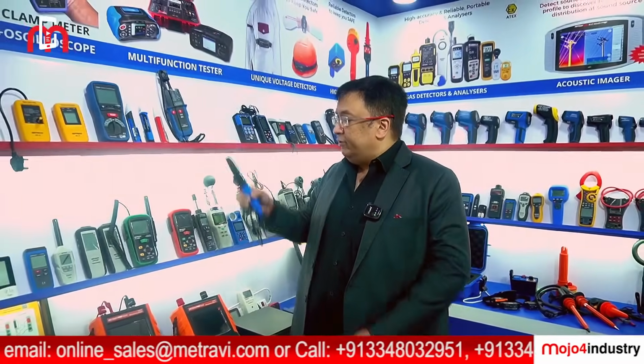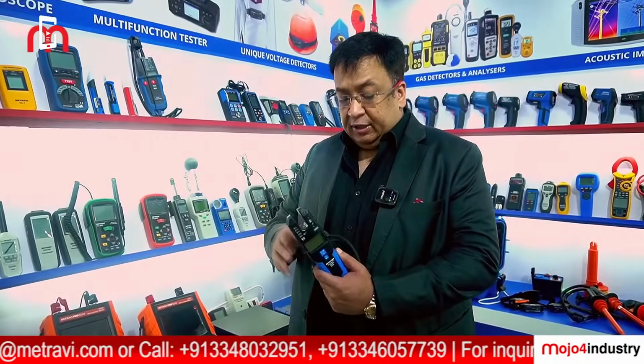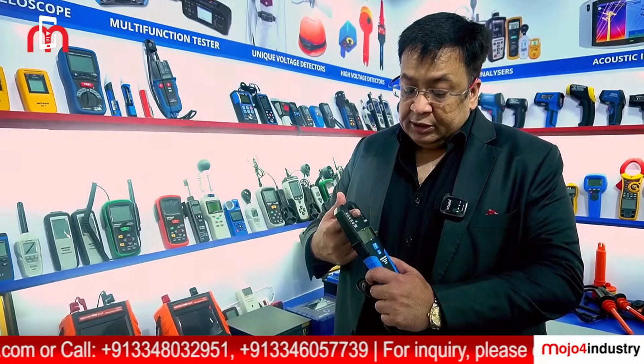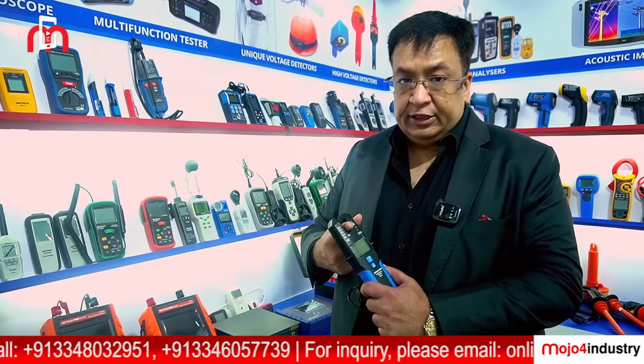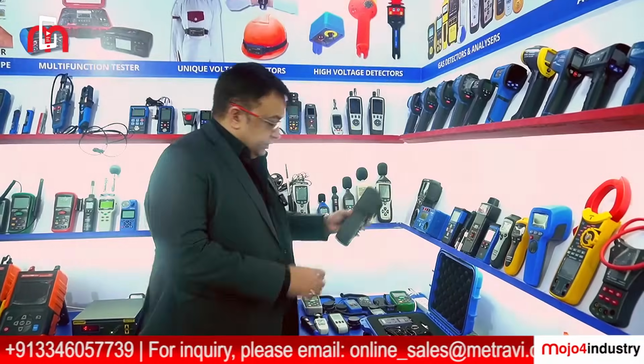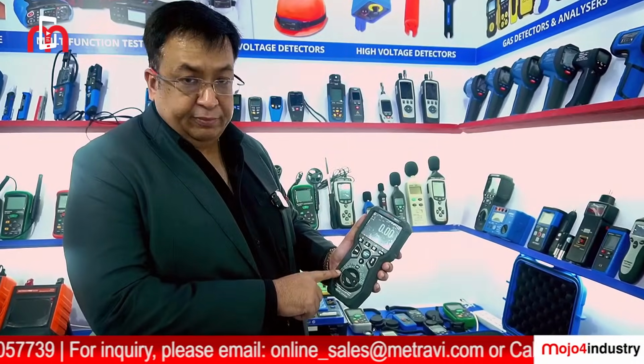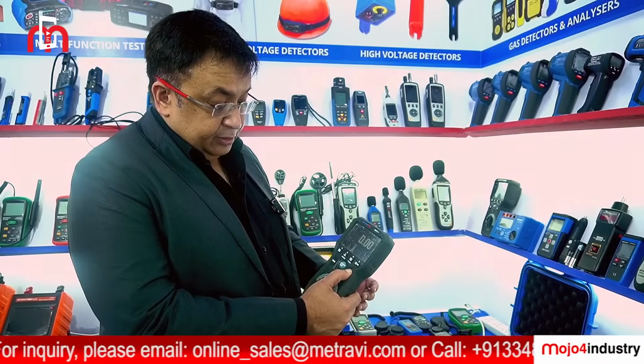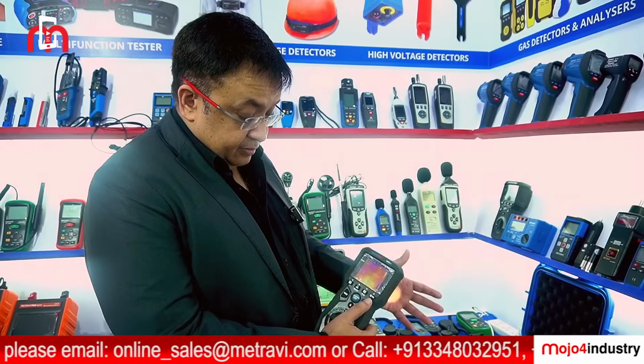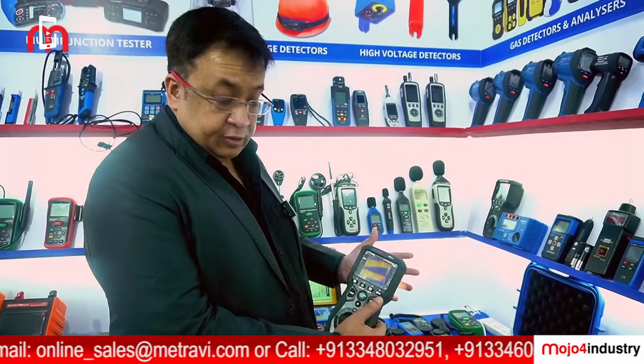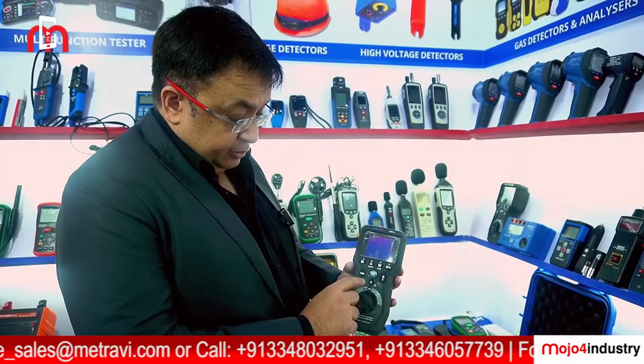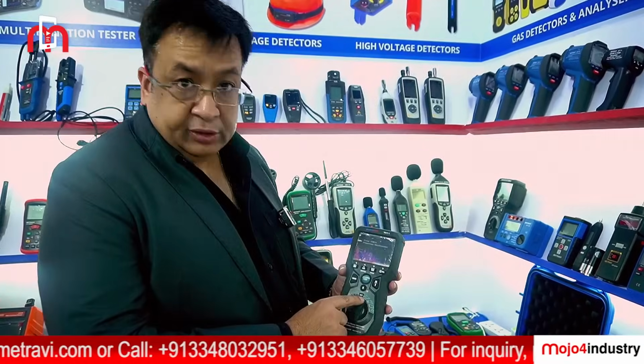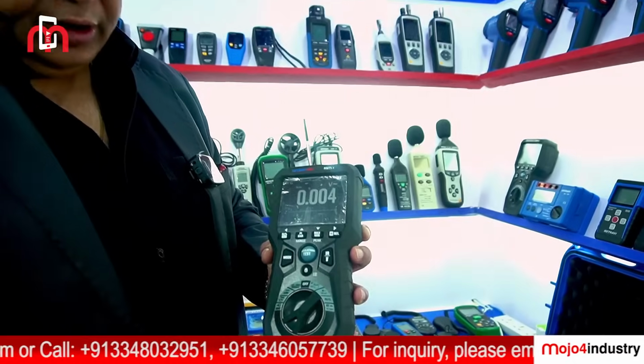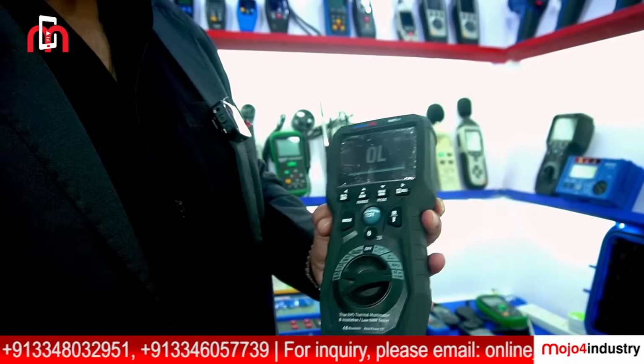Now this is a new instrument that we have for photovoltaic application. You don't have to choose whether the voltage is AC or DC; it will automatically detect whether the measured voltage is AC or DC. Even when you keep the cable inside, you don't have to choose whether it is AC current or DC current. It will automatically choose. This is the only open-jaw clamp meter that can measure DC current as well. This is a multifunction instrument for measuring high current up to 3000 ampere and temperature, and you can do thermal imaging as well. You have low resistance measurement, insulation resistance, voltage with VFD, DC voltage, frequency, and resistance measurement.